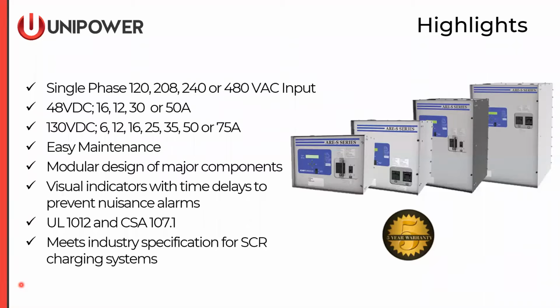So these are single phase. Again, we're talking about the ARE-S. They're single phase chargers, 120 to 480 AC input. We have in the 48 volt flavor, 16 to 50 amp, in the 130 volt flavor, 6 to 75 amps. Again, there's a chart at the end that outlines all these models.